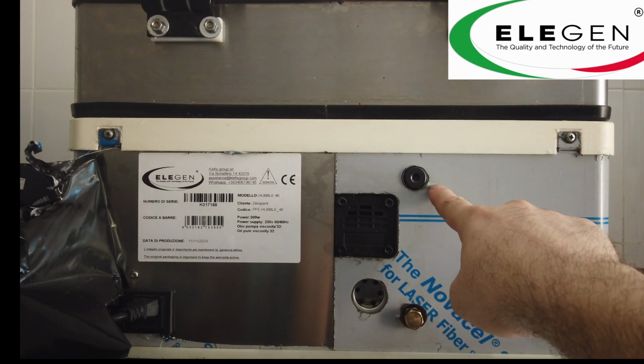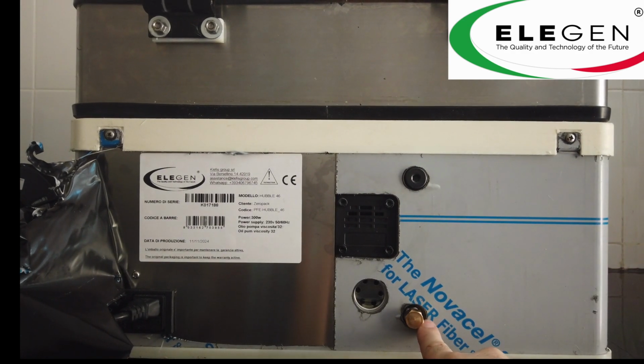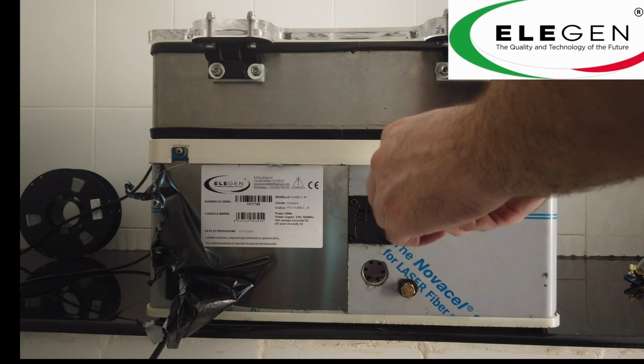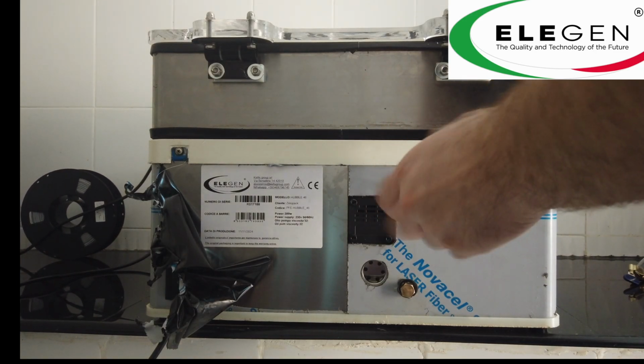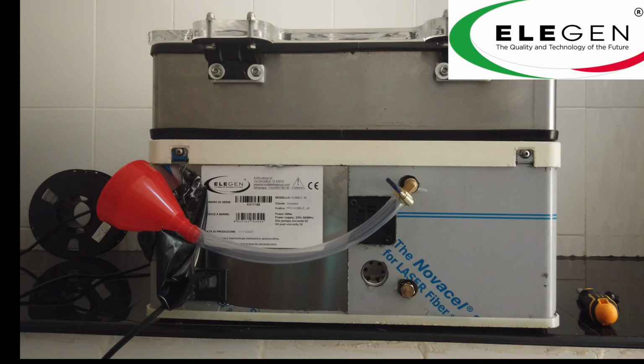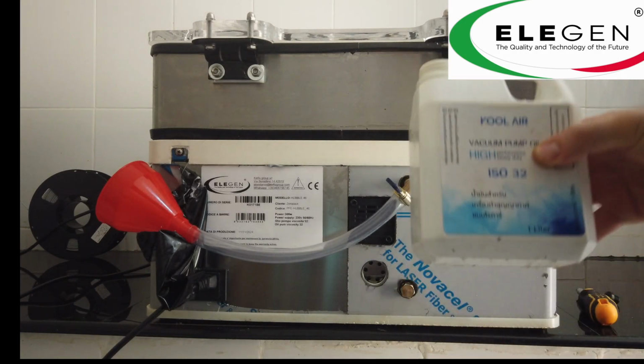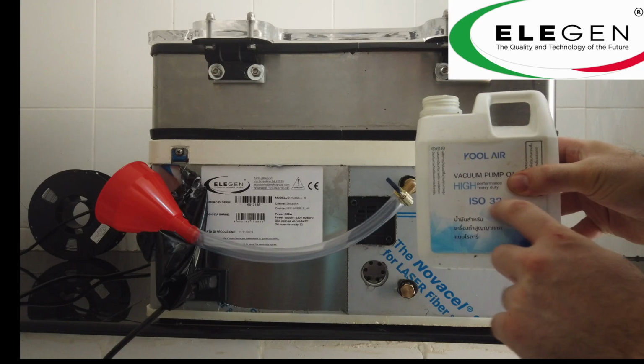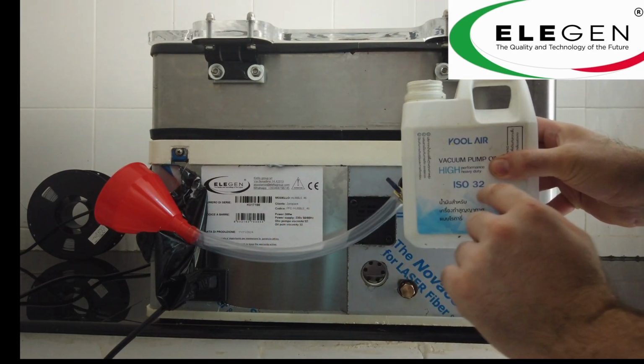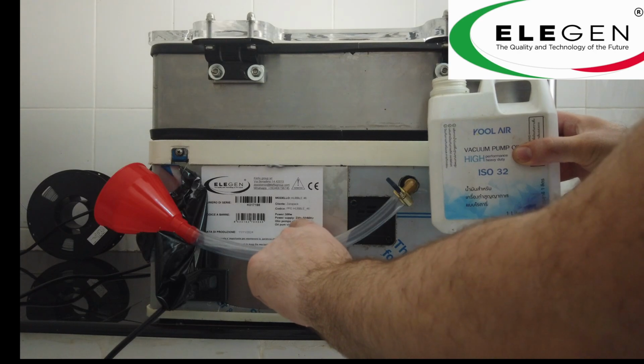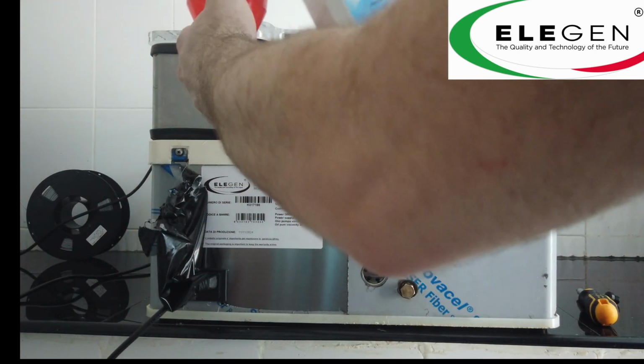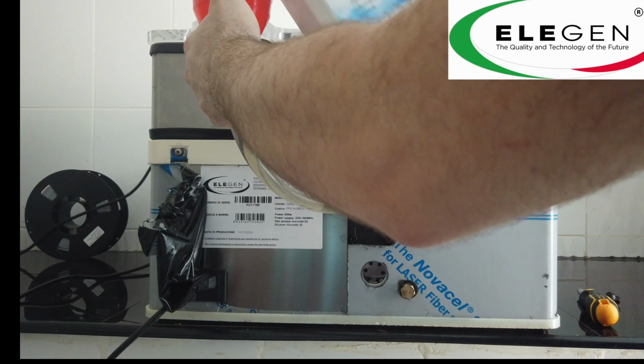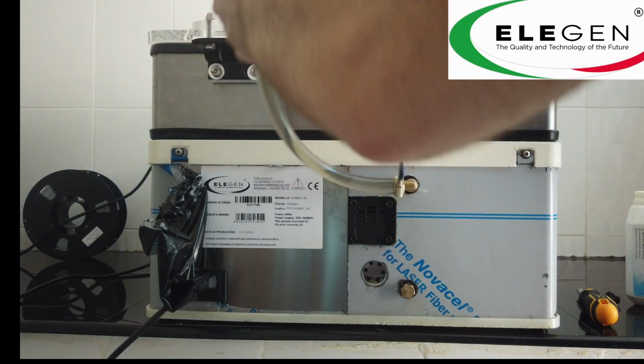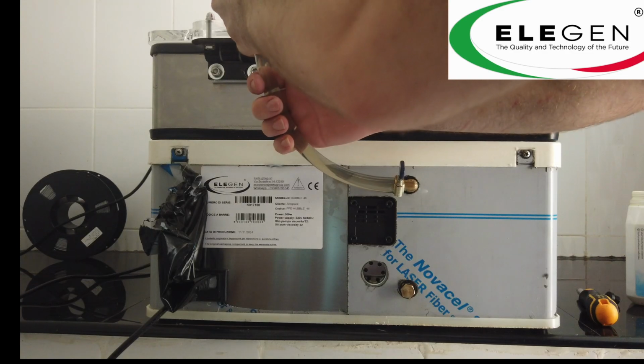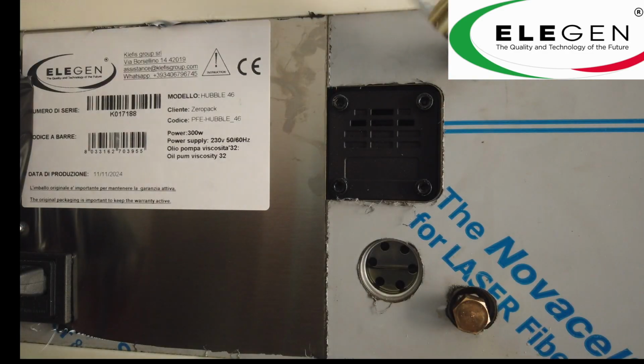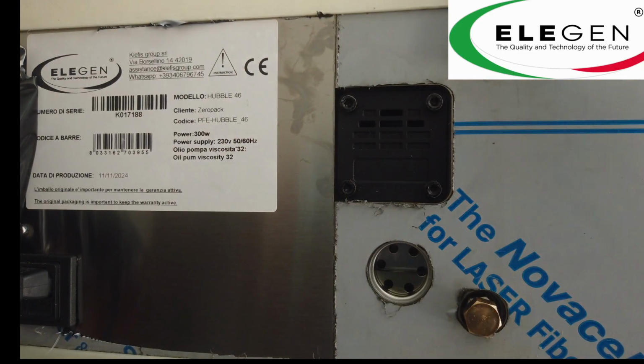On the back you will also find the oil inlet, the oil drain and the oil level port. Unscrew the oil filler fittings and insert the accessory into the hole, screwing it in just enough. Next, check that the oil you are inserting has the same viscosity as represented on the serial number. Then proceed to insert the oil into the pipe and fill the pump until the porthole is about half full. Now unscrew the oil filler attachment and screw the cap back on securely.